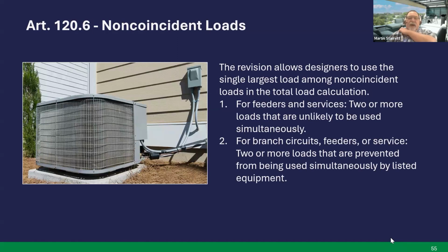Non-coincident loads. The revision allows designers to use the single largest load among non-coincident loads in the total load calculations. For feeders and services, two or more loads that are unlikely to be used simultaneously. For branch circuits, feeders, or service, two or more loads that are prevented from being used simultaneously by listed equipment. They've cleaned this article up real good. It's more straightforward now. You don't have to jump through a whole lot of hoops. Basically, you'll be choosing the larger of the two. Next slide.